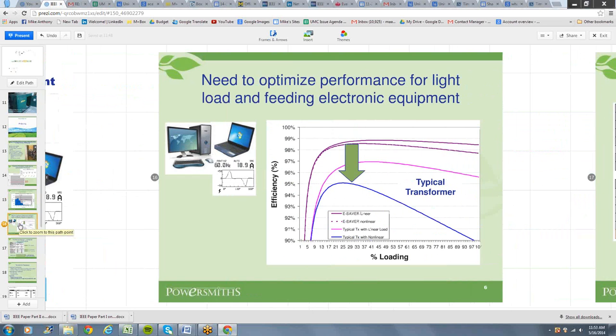The second thing you've got to consider is what we are connecting to transformers. We are connecting electronic equipment, and we're not connecting incandescent light bulbs anymore. What that means is that the load profile is important. If you look at electronic equipment, single phase in this case, so stuff you plug in at 120 volts, it draws pulses of current instead of current continuously.